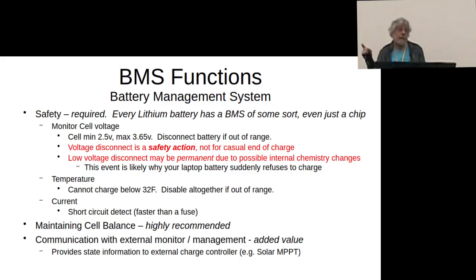Short circuit detect - has anybody dropped a wrench across a lead acid battery and lived? Big things happen when you do that. If you drop a wrench across a lithium iron phosphate battery, it bounces off and you almost think nothing happened. What happened was the BMS detected the short circuit and turned it off instantly - the fuse didn't even have a chance to blow. People are really scared about lithium batteries being so powerful - yeah, they are, but they're also a whole lot safer because of things like that.